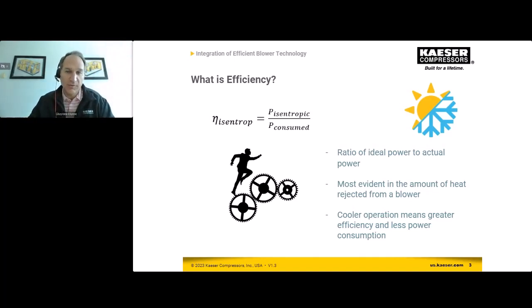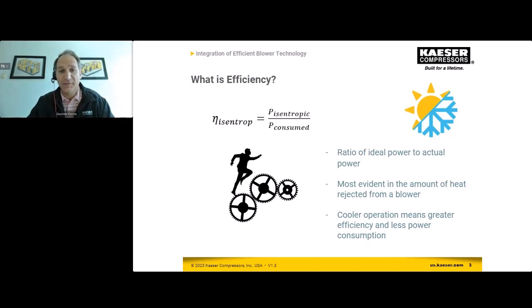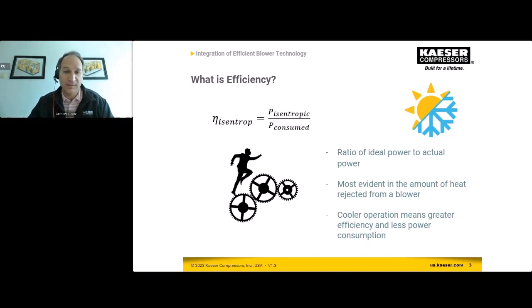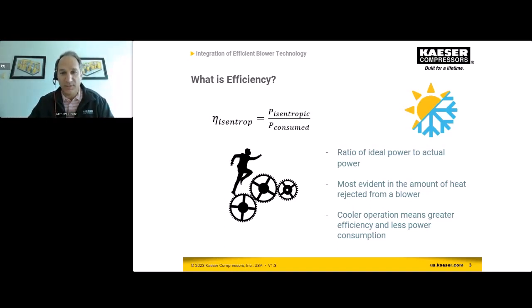A way to bring that home is that inefficiency shows up in heat and the amount of heat being rejected from a blower. A more efficient blower means it runs much cooler. This is beneficial for many reasons: the machine runs cooler mechanically, keeping oil, lubricants, and components cooler; there's reduced heat rejected into the room where the equipment sits; and the discharge air coming out of the blower is cooler, which is better for your process, system, and the wastewater aeration.